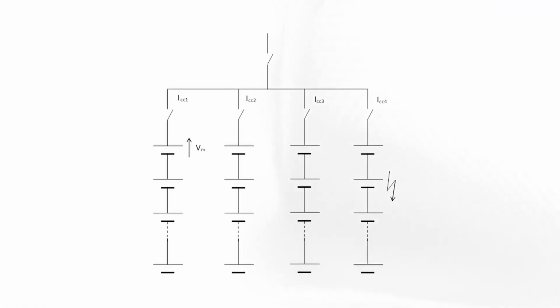Another challenge is to consider the parallel functioning of many racks on the same DC bus. In this case, it is necessary to evaluate all the possible faults that can occur. For example, you can have a fault on the external terminals of a single module of the rack, and in this case, it is necessary the intervention of the internal protections of the modules, because the current flowing in the external DC protection is too low to allow the intervention of these protections.